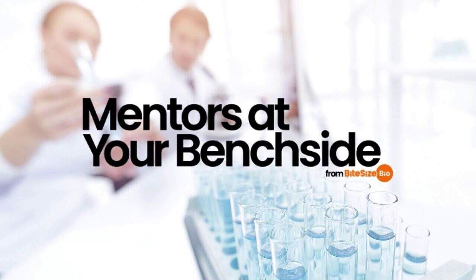Before putting tubes in the rotor, it's important to consider, can the tubes you're using withstand the temperature you want to centrifuge at? Can these tubes safely hold the solution in them? For example, plastic tubes will fall apart when there's chloroform in the solution. It's therefore important to consider what kind of solution is being centrifuged. Do the tubes need to be filled completely? Some tubes crush in if not filled completely, for example heat-sealed tubes.